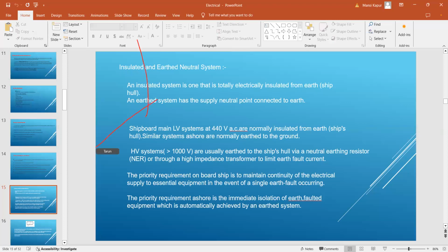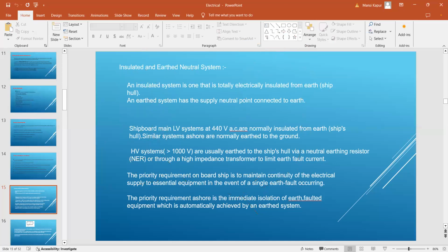Suppose this was your generator, this was the neutral point and you earth it, and here one earth fault occurs at the motor. So a large current will start to flow from here, right? Because the current takes the path of less resistance, right? Yes, sir. And when a large current flows, the overcurrent relay at the motor is going to open the breaker, right? And if this breaker does not open, your generator is going to get overloaded. So our first aim on board the ship is to run the machinery even with a single earth fault. Suppose this is your steering gear motor, and because of the single phase fault your motor is tripped and you are in maneuvering waters, so you are in deep trouble now, right? So that is why our first priority on board the ship is to keep the equipment running.